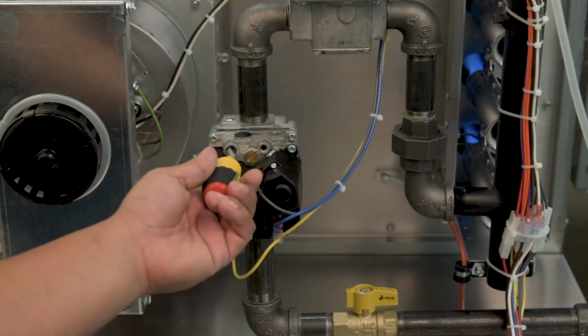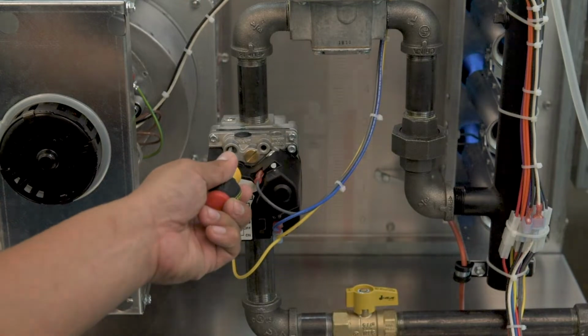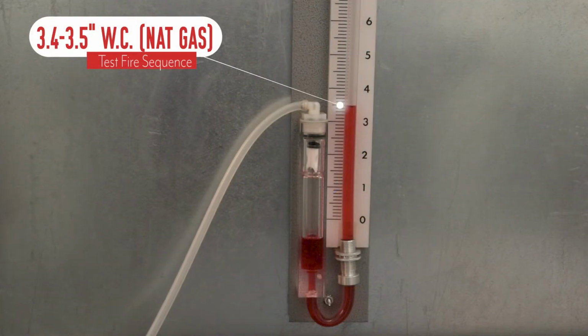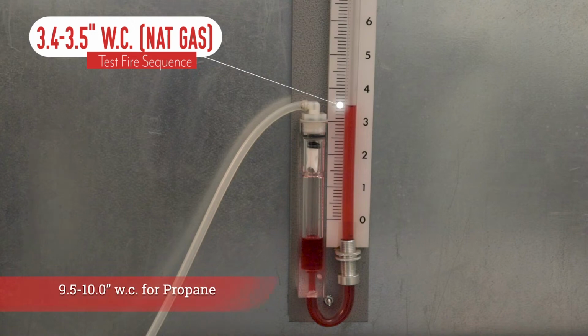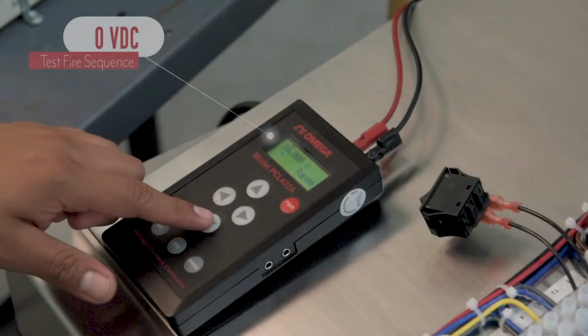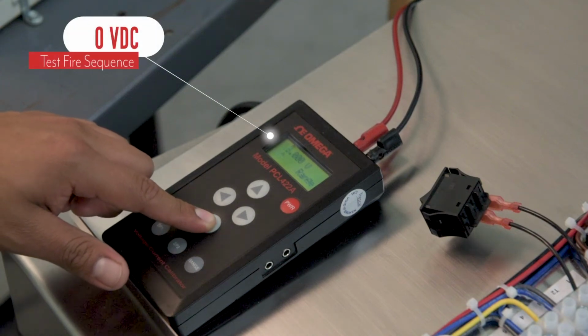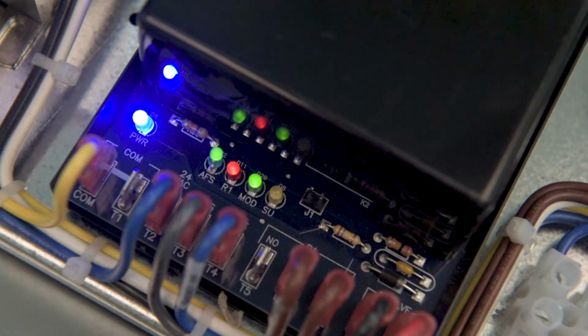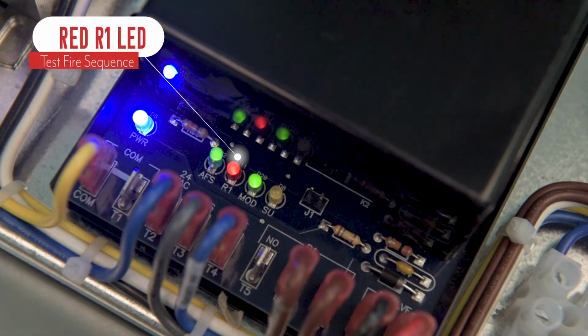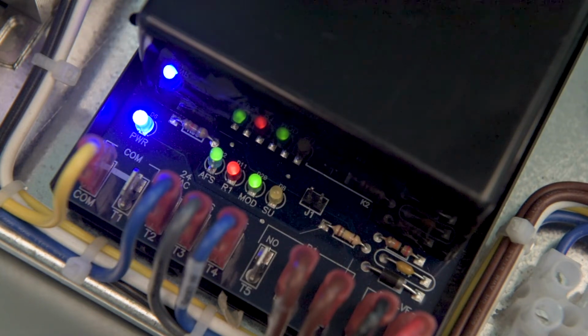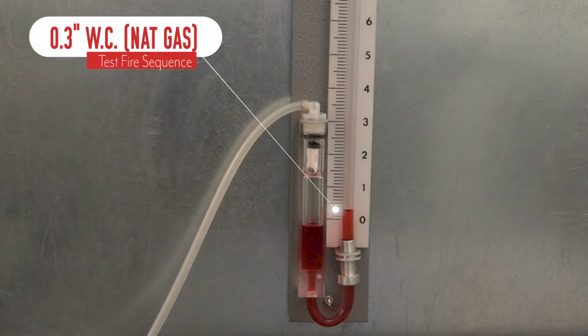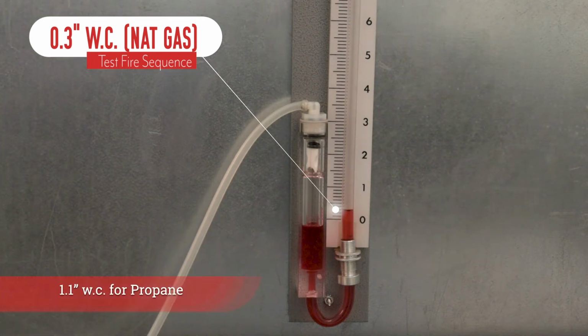Set high fire by adjusting the regulator on the combination gas valve to obtain 3.4 to 3.5 inches water column for natural gas or 9.5 to 10.0 inches water column for propane. Reduce the analog input voltage to 0 volts DC. The inducer fan will drop to low speed and the red R1 LED will turn on. Depending on the heater model, the green AFS LED may be on or off. Verify the manifold pressure is 0.3 inches water column for natural gas or 1.1 inches water column for propane.